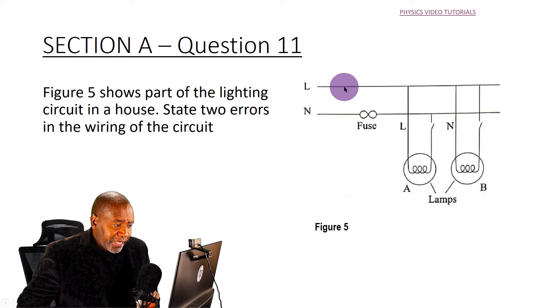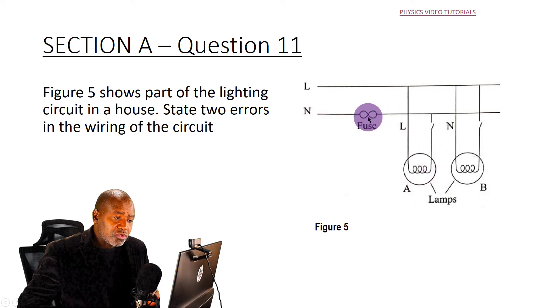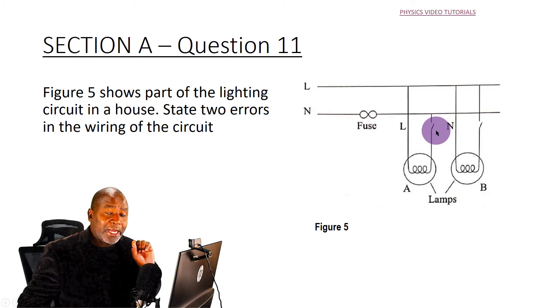When we follow the live wire, we get to the lamp, and then after the wire comes from the lamp as it goes to the neutral, we have the switch connected. So we can directly see that for lamp A, the switch is not connected correctly. It's connected to the neutral instead of the live wire.